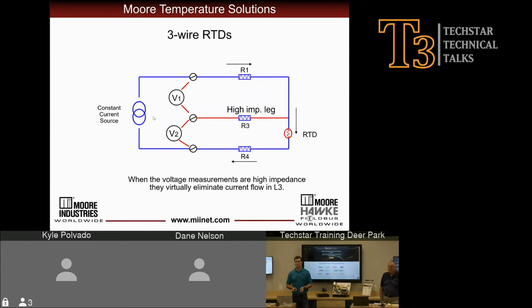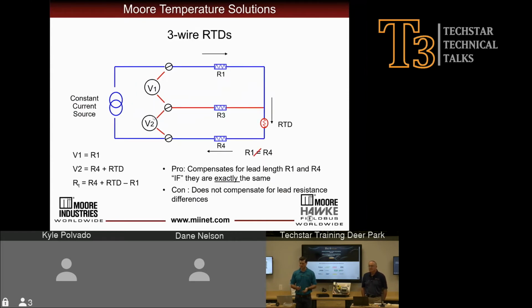The 3-wire RTD introduces an additional leg that's high impedance and has no current flow in it. So essentially, there's no voltage drop over that third leg. So now when we're passing that constant current source over our RTD element, we're taking the resistance of the leg R1, and we're taking the resistance of the leg RTD and R4. Where the voltmeter leads in, that includes the RTD element and R4 as the resistance that we're capturing in that measurement. So this is a pretty accurate temperature measurement if the lead legs R1 and R4 are identical.